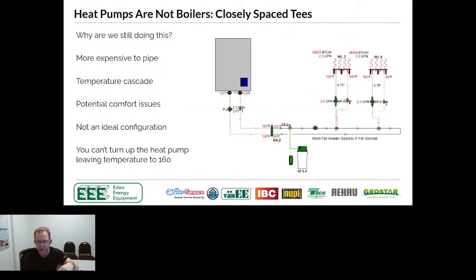I've set it up on, let's say, an air to water, not a boiler. Well, the maximum water temperature that an air to water can put out, I don't care whose name is on it in North America, is 140 degrees. And at 140 degrees, that's the max. We're not saying we necessarily want you to be sitting at 140 all the time any more than we want somebody trying to run a condensing boiler at 190, 195 degrees. So in this scenario where I've got a boiler that say can do 180 degree water, the closely spaced tees doesn't matter. The temperature cascade doesn't matter because if the first one's getting 180 and you put a mixing valve on it, the very last one still has enough BTUs to heat the space.